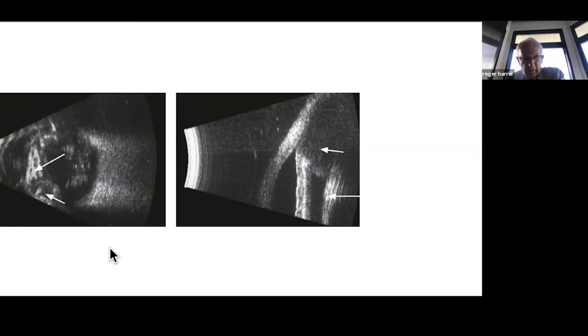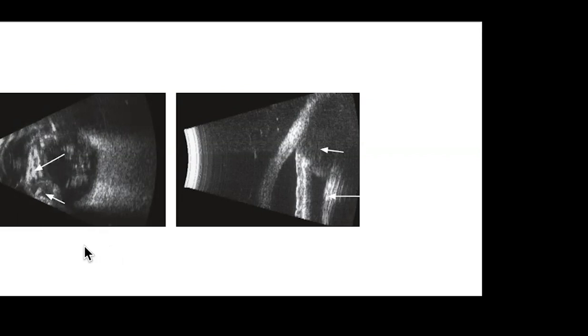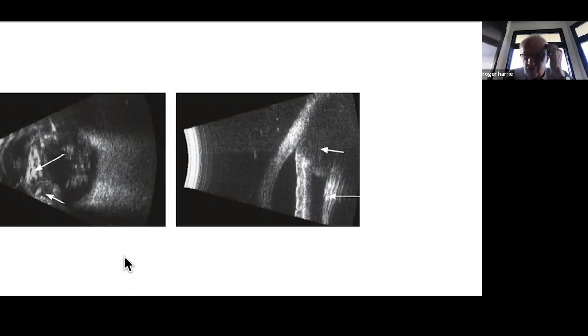Silicone oil significantly affects ultrasound measurements. An eye filled with silicone oil appears artificially elongated on B-scan — the retina appears far away and the image looks unusual. This is because silicone oil slows sound velocity to approximately 1,000 m/s compared to the normal vitreous velocity of 1,532 m/s. The machine interprets the longer travel time as a longer eye, producing artifactually large axial length measurements — typically 30-35 mm.